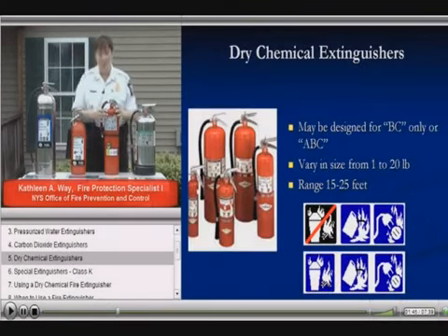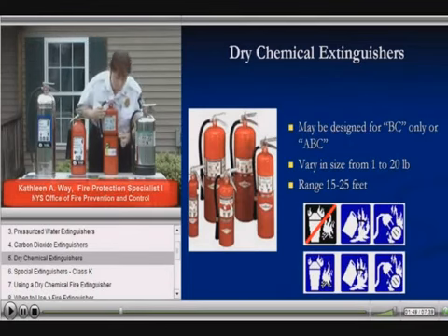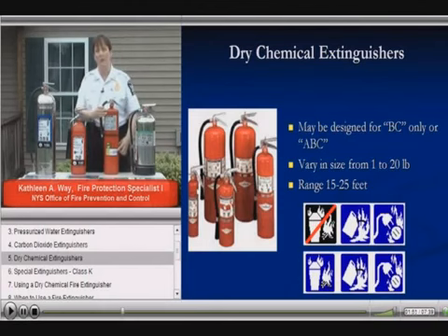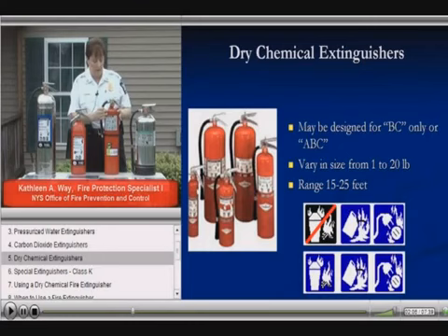The fire extinguisher that we're going to be talking mostly about is the multi-purpose dry chemical fire extinguisher. As you see from the pictogram on the front, it's used to extinguish Class A, B, and C fires. Class A fires being wood, paper, household rubbish, some plastics. B being flammable liquid fires, and C, energized electrical fires.